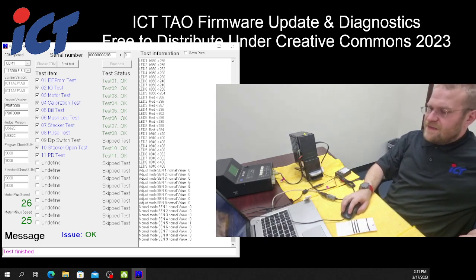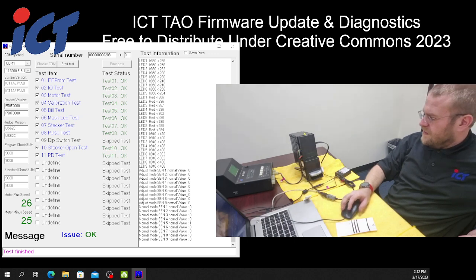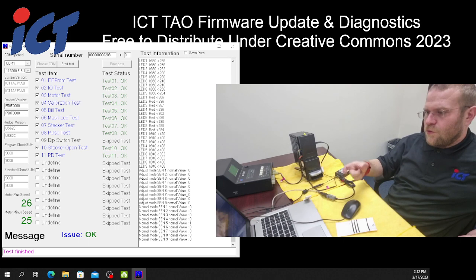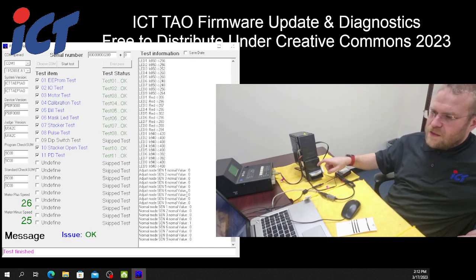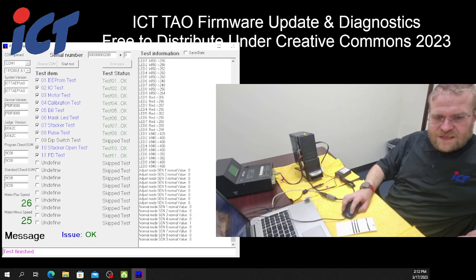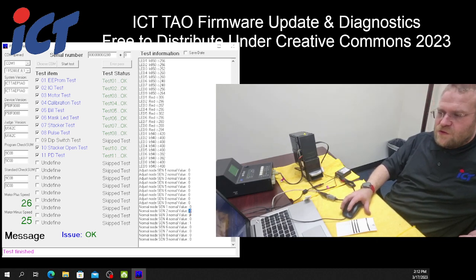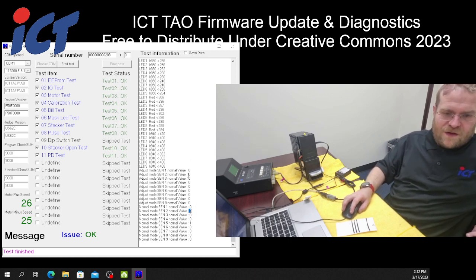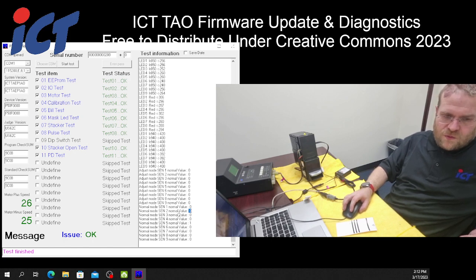The last test is the PD test. That is going to be specifically for your sensor board, which is the one in the pull-out tray, not the upper board, but the one in the lower. If there's any problems in the sensor board area, you'll also be notified by a message saying, value 14 NG or value 6 warning. If you do see a warning, that means it's still technically within range, but is getting on the outer edges of it and may start leading to sensor problems in the near future. So if it's warning or NG, you would probably want to replace the sensor board on that unit that you're testing.